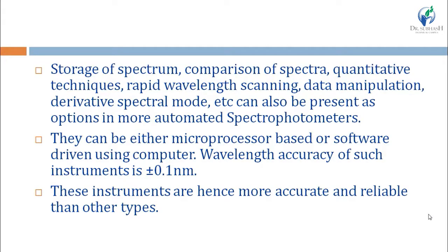In spectrophotometer, additional capabilities include storage of spectrum, comparison of spectra, quantitative techniques, rapid wavelength scanning, data manipulation, and derivative spectrophotometry. All these can be present as options in automatic spectrophotometers. They can be microprocessor-based or software-driven using a computer, making wavelength accuracy ±0.1 nm only. These automated spectrophotometers are more accurate and reliable than colorimeters and spectro-colorimeters.